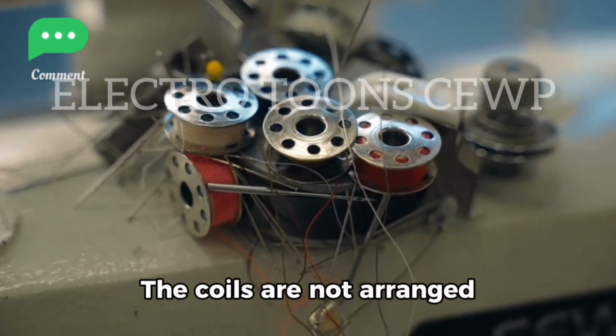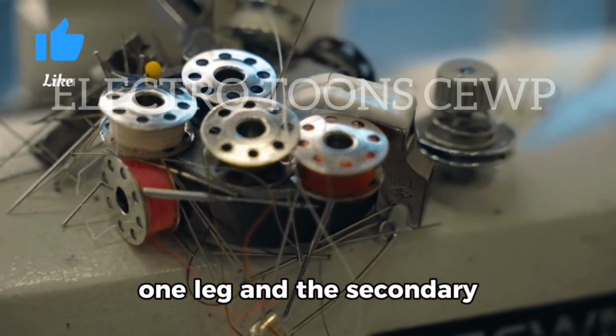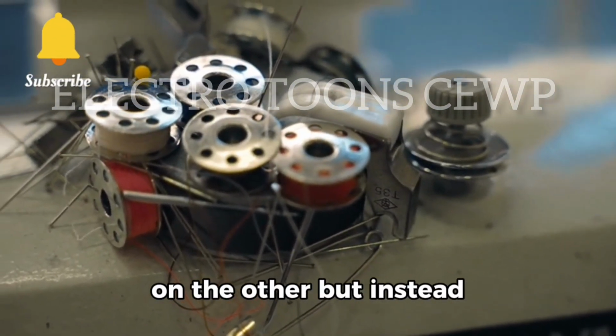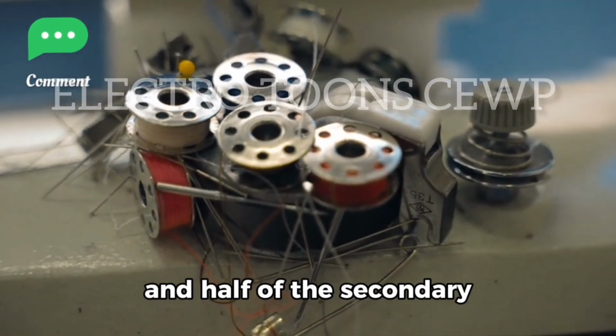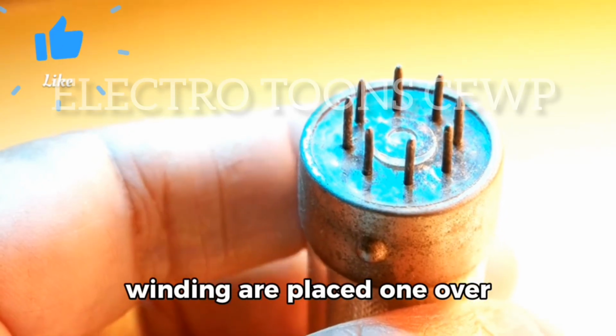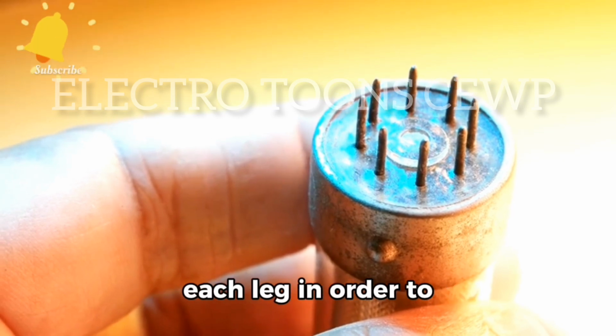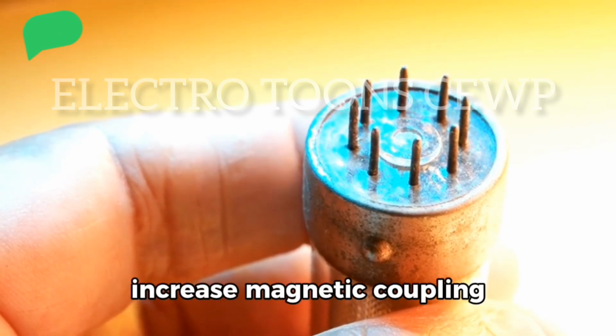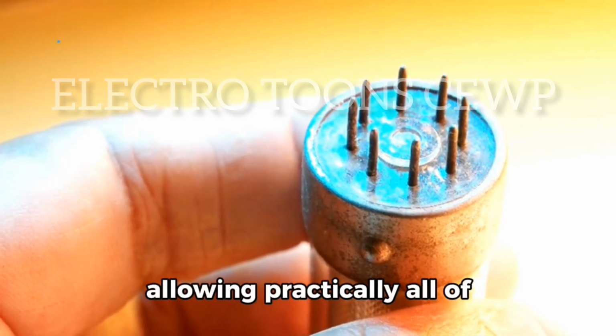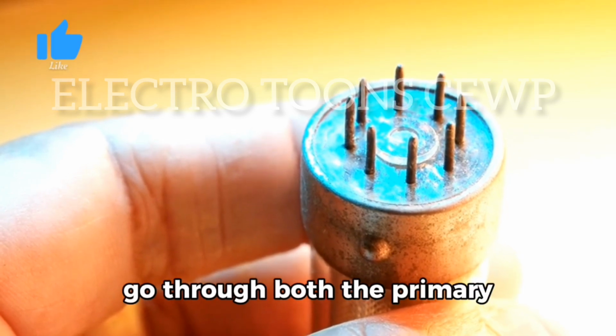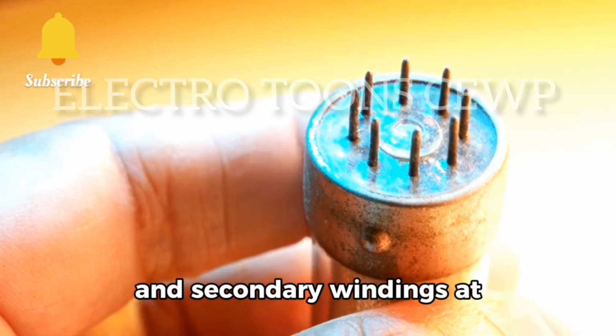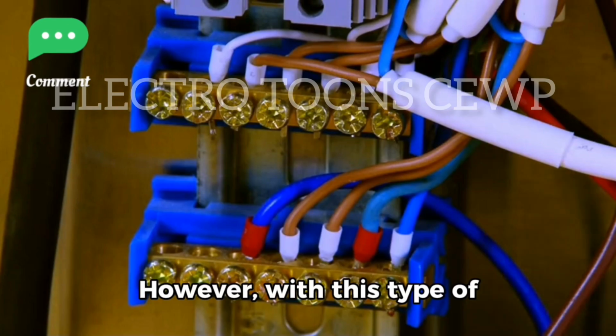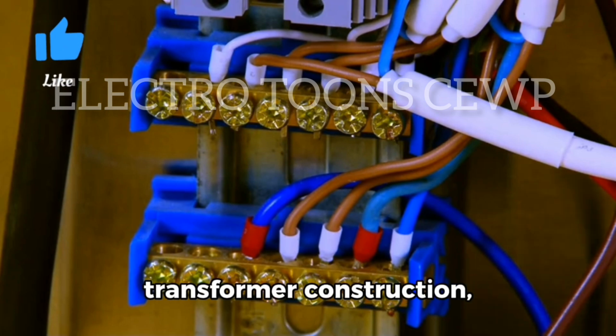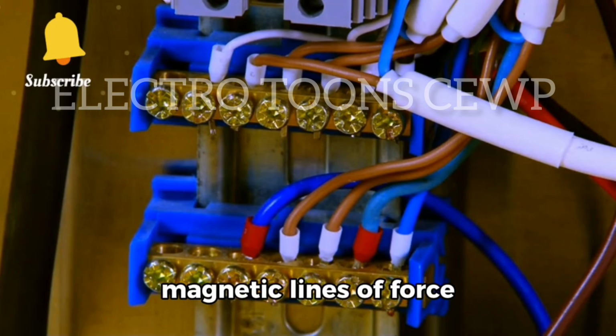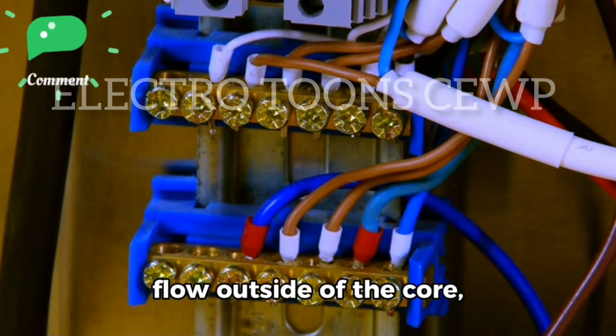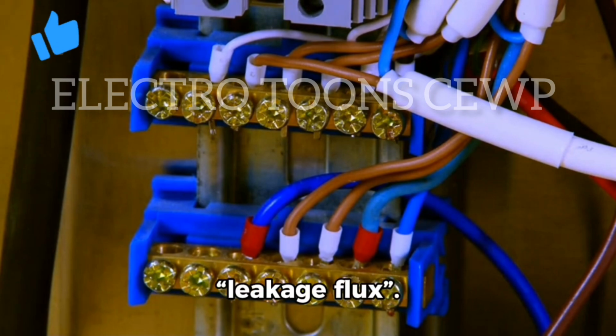The coils are not arranged with the primary winding on one leg and the secondary on the other, but instead half of the primary winding and half of the secondary winding are placed one over the other concentrically on each leg in order to increase magnetic coupling, allowing practically all of the magnetic lines of force to go through both the primary and secondary windings. However, with this type of transformer construction, a small percentage of the magnetic lines of force flow outside of the core, and this is called leakage flux.